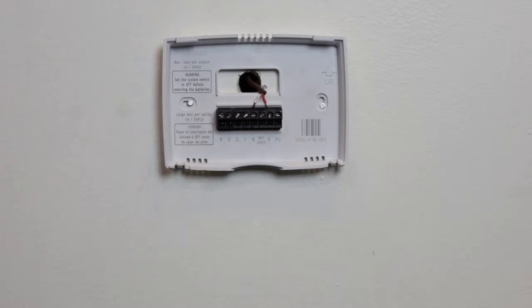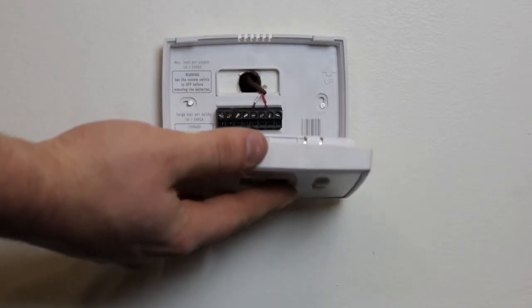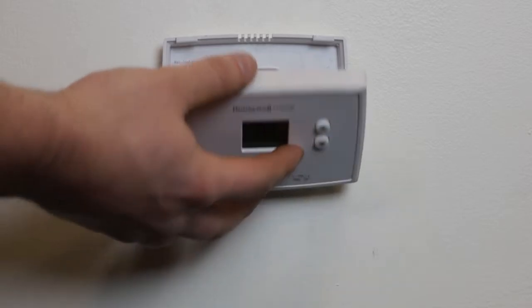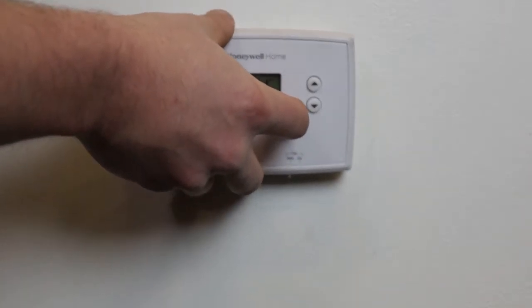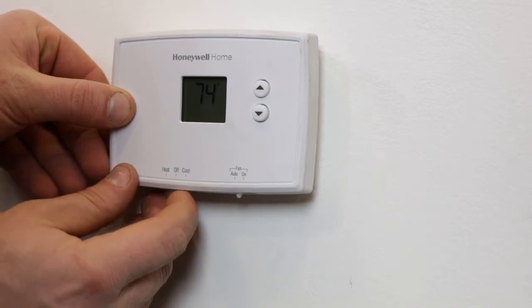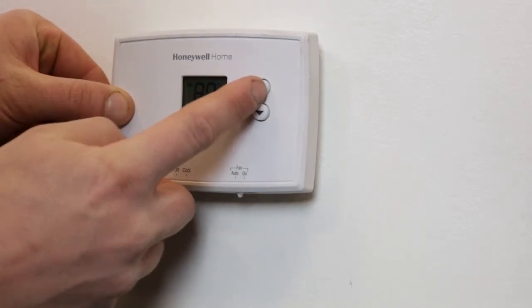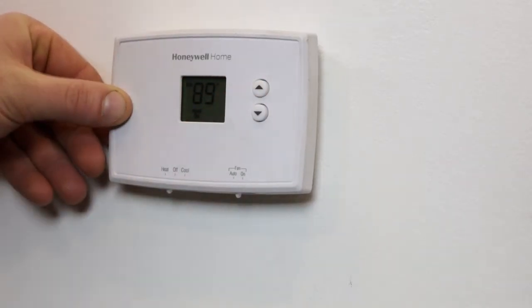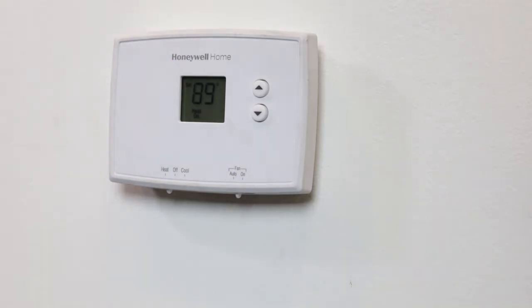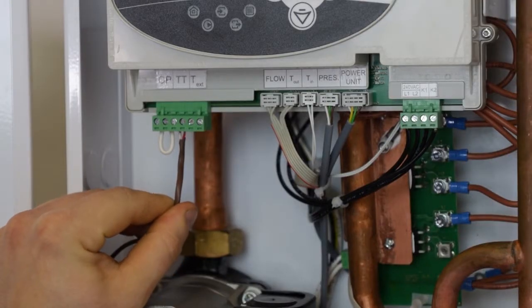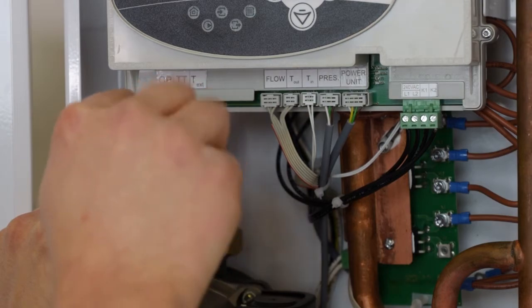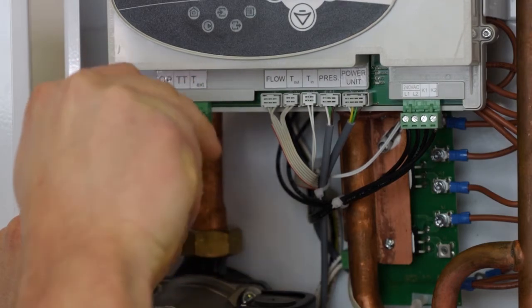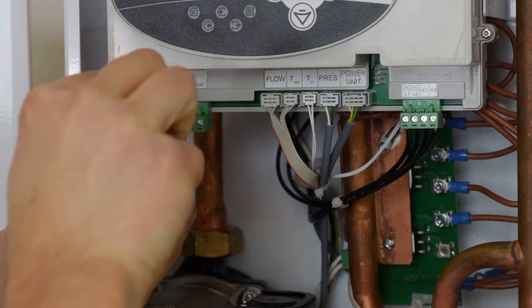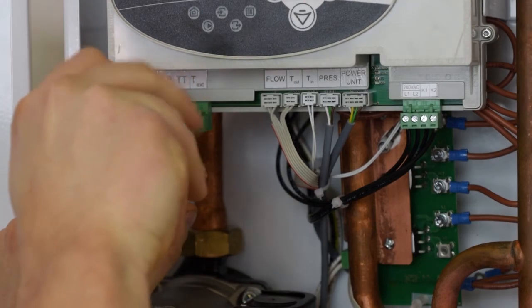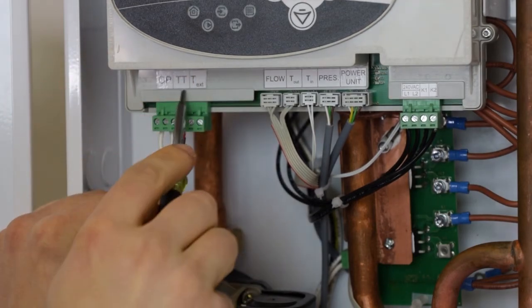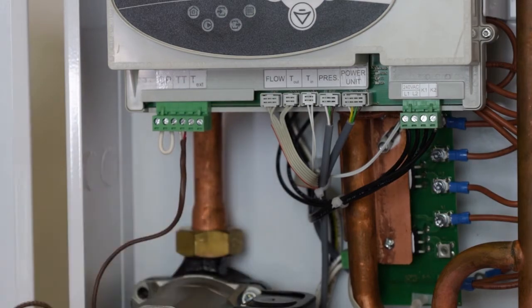The next item we will go over is the thermostat. The boiler can be signaled to turn on from a standard 2-wire thermostat. These connections should all be voltage free. Connect the 2 18-gauge thermostat wires from the thermostat to the TT connections on the bottom left of the control panel. You can utilize the additional knockouts to gain access to the control panel. Always make sure to place the thermostat in a place where it cannot be influenced by other heat sources.